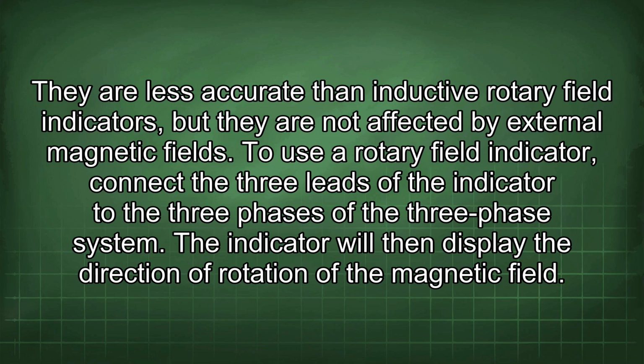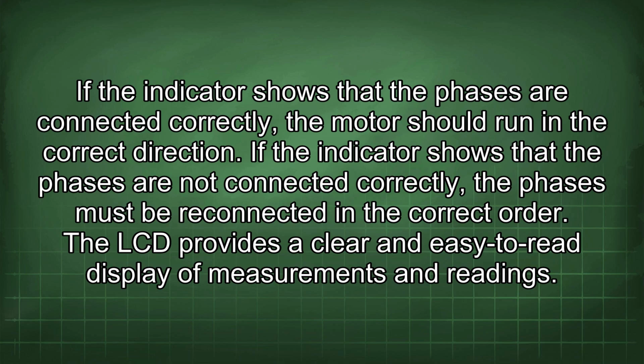To use a rotary field indicator, connect the three leads of the indicator to the three phases of the three-phase system. The indicator will then display the direction of rotation of the magnetic field. If the indicator shows that the phases are connected correctly, the motor should run in the correct direction. If the indicator shows that the phases are not connected correctly, the phases must be reconnected in the correct order.